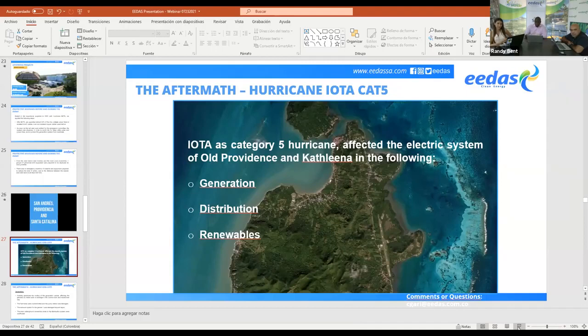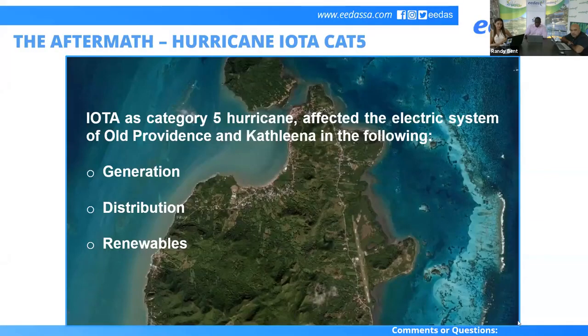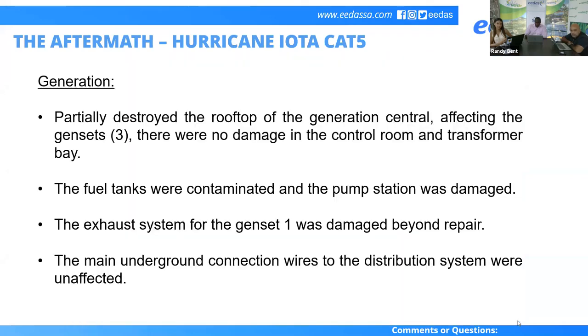In generation, the plant is located in a well-protected area, one of the areas that suffered less damage. Basically it affected the rooftops of the gensets, with water and heavy rain. The fuel tanks were contaminated, several pipelines were broken, and the pump station at ground level was damaged. The exhaust system of one of the gensets, the smallest one, was damaged beyond repair. But the main underground wiring system and the transformer bay were unaffected.